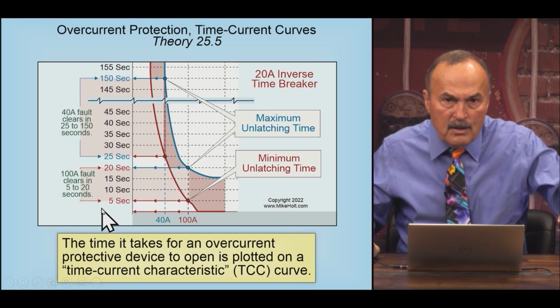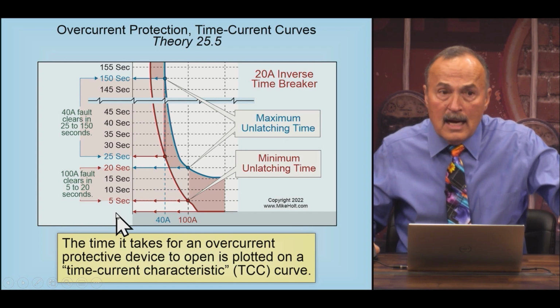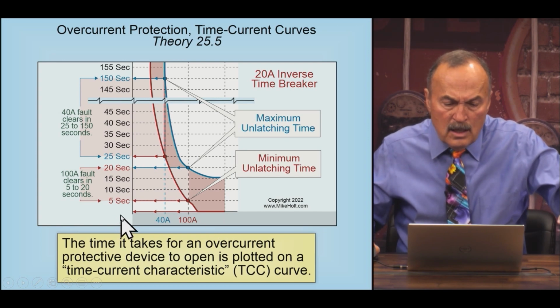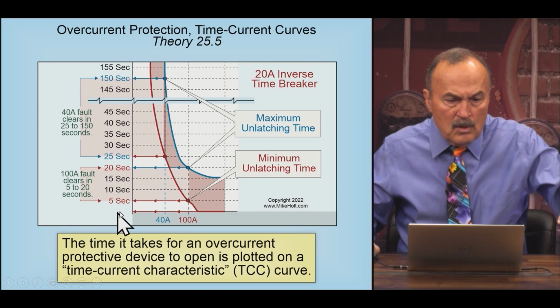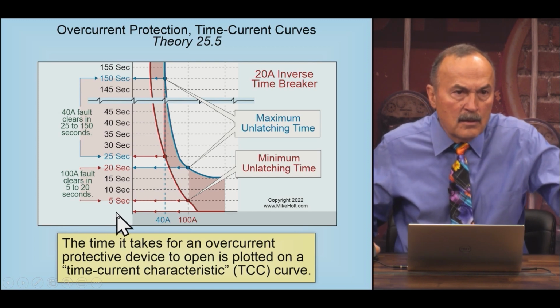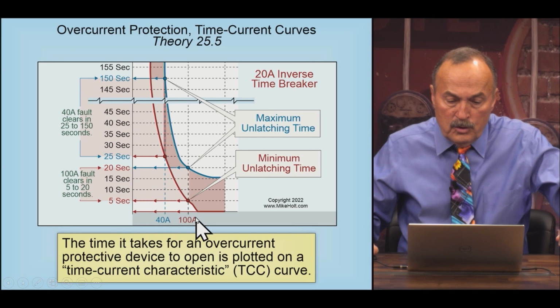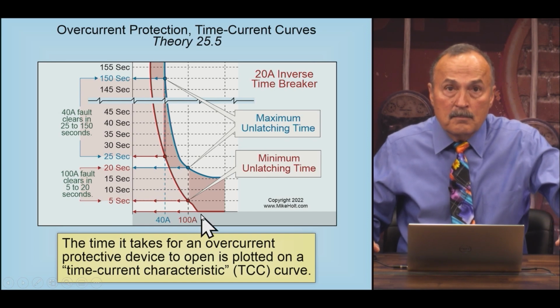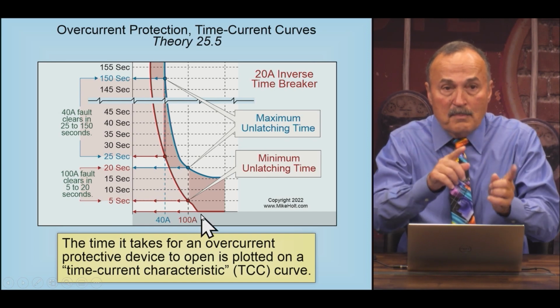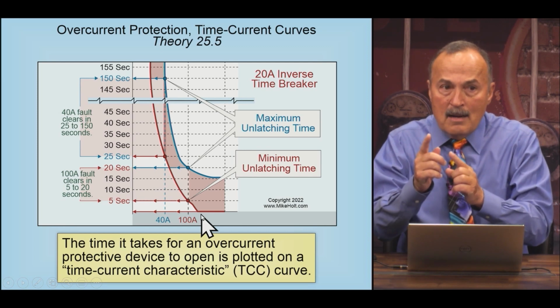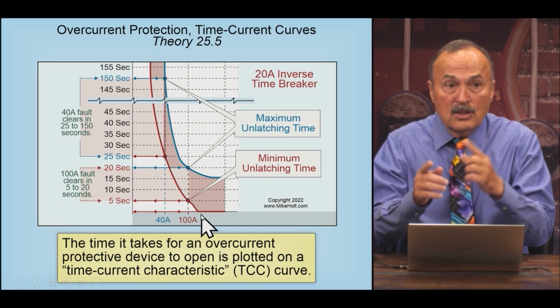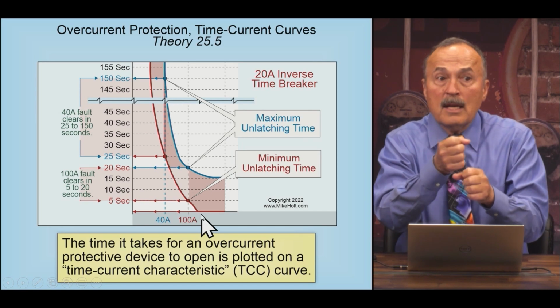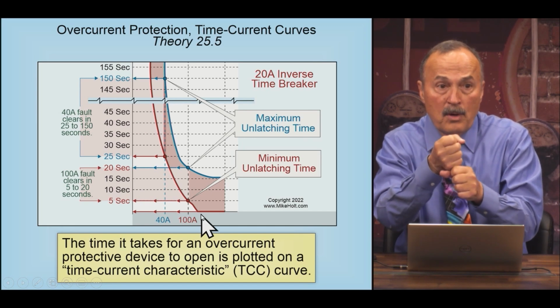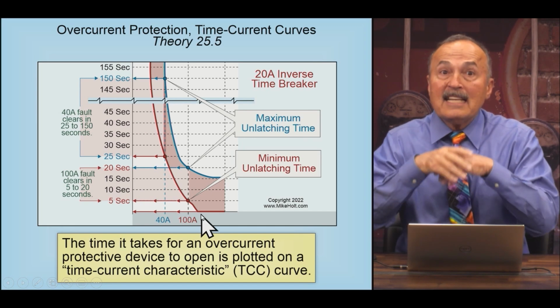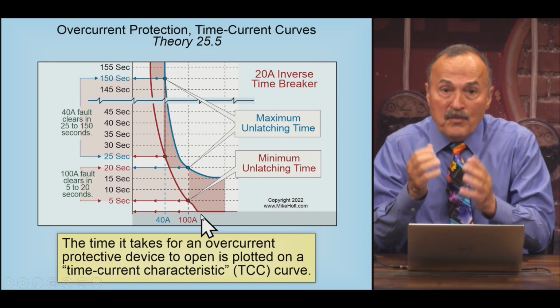Maybe we can put some value down here, Brian, on the left-hand side, of some very, very low amount of time. And Tom, at instantaneous, if we're going to put a number here, what would be a reasonable number, in seconds? 0.01. Okay, so if you had 500 amps, but Tom, correct me if I'm wrong, when we go to 500 amps, this is not an overload condition. This is a short circuit condition, and that was where the armature inside the breaker that was latched, it's an electromagnetic field.